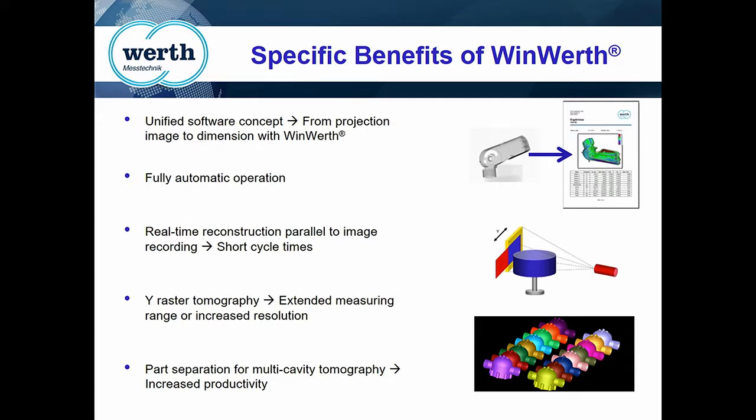The nice thing about the individual parts is that once you write a measurement program, or you save the measurement program, we have an automatic loop function. So you can loop it through, and each one of those parts will get measured the same way. You can just loop it, and you go bang, bang, bang, bang, bang, and it's very, very quick. While it's reconstructing and doing the measurements, the operator can be changing it, or it can be the robot changing it, but you can have pallet changers. But no, for true tomography, you can't just hit it from one side.